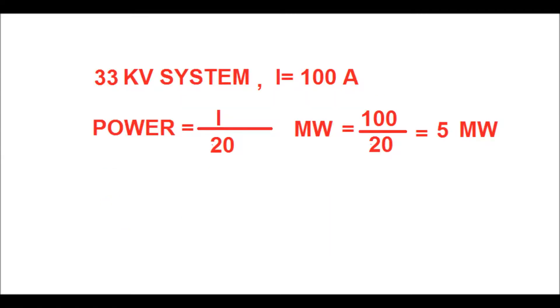For a 33 kV system, if current is 100 amperes, then to get the power in megawatts you have to divide the current by a factor of 20. You will get 100 divided by 20 equal to 5 megawatts.